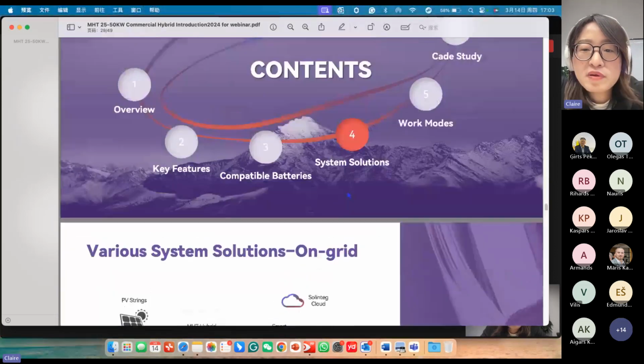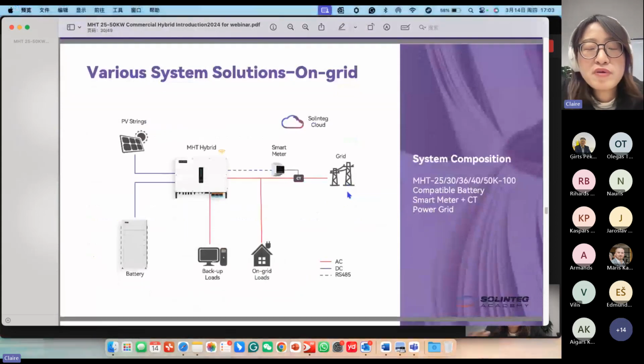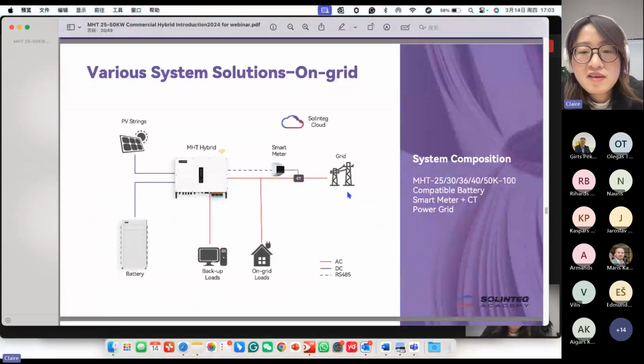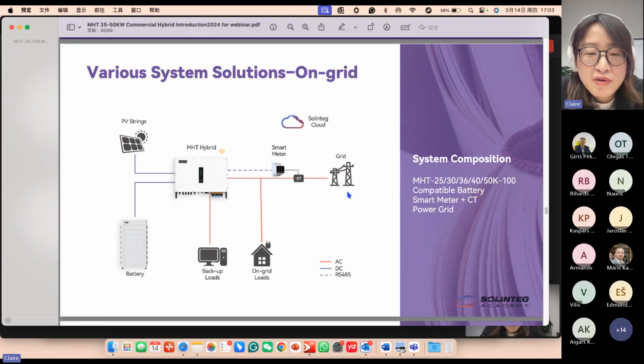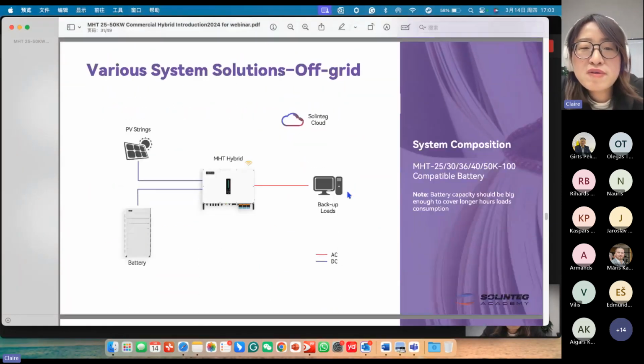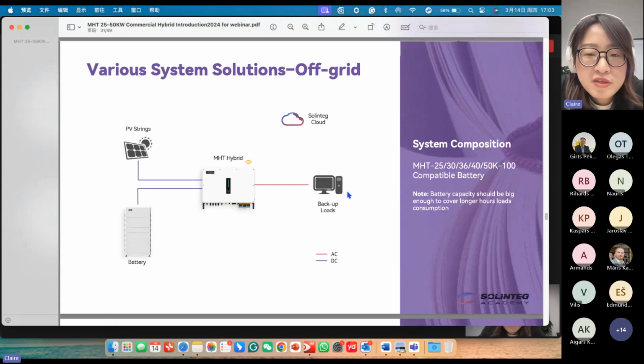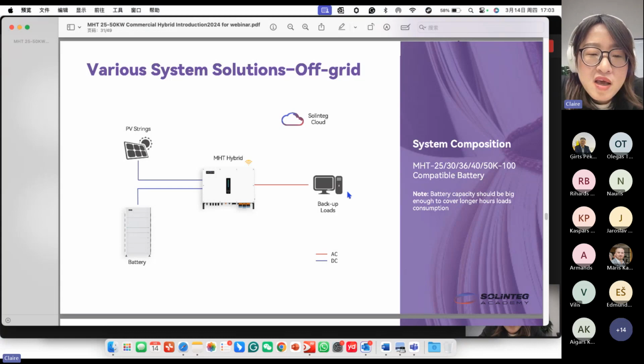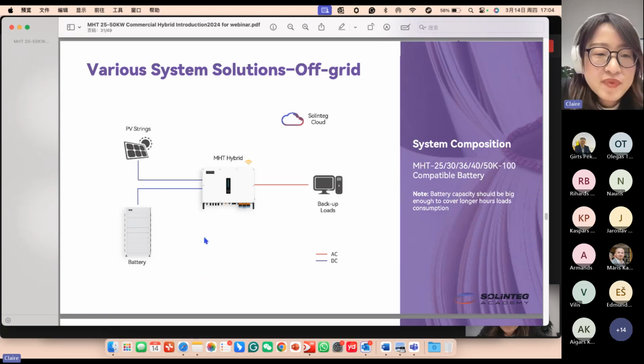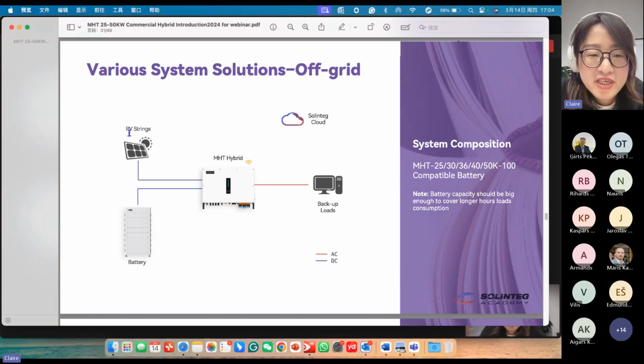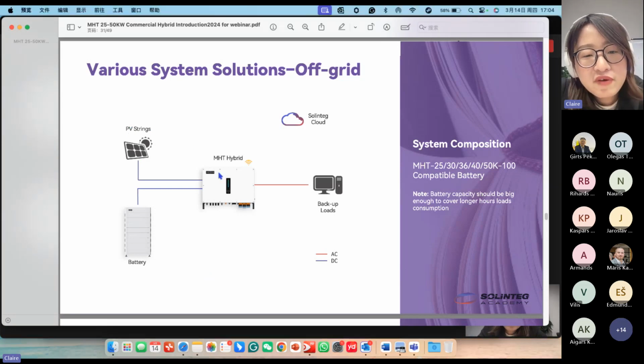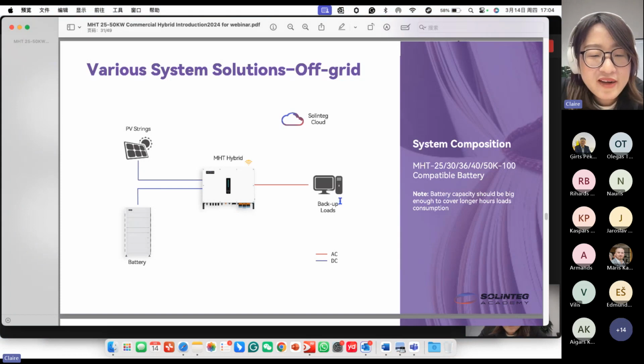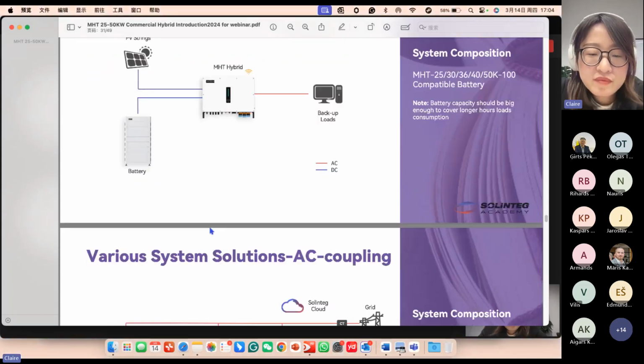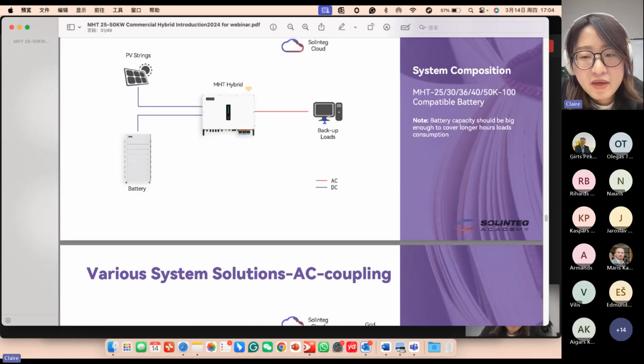So the next part is the system solution. We can see our inverter can be used in different situations, like the very basic situation, on grid. This part we all know, so no need to talk more about it. And we can also be used in a purely off-grid situation. In this situation, if you have a battery connected, the inverter can work smoothly for a very long time. In the daytime, the PV generates DC power that goes to the inverter, and the inverter converts it to AC to supply the loads. If there is excess power, it can be used to charge the battery. And at night, the battery discharges to supply the loads.